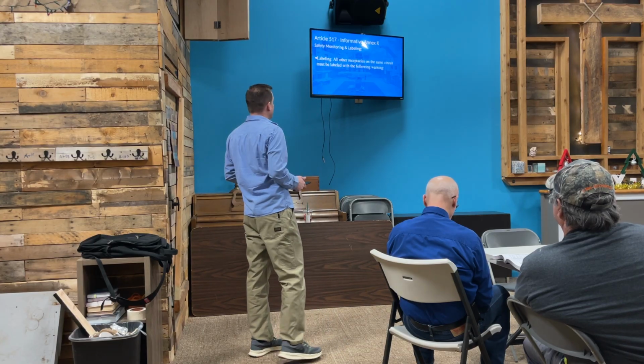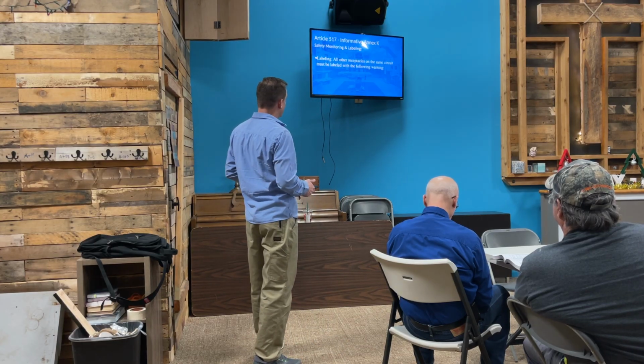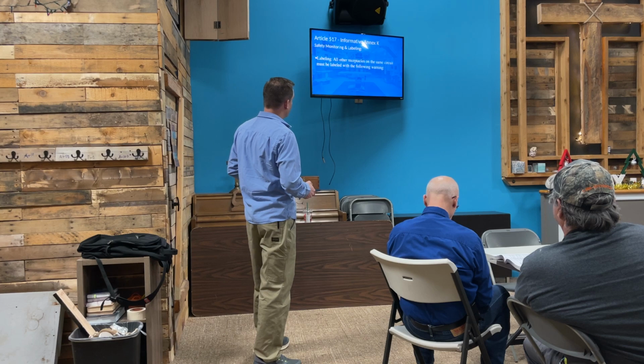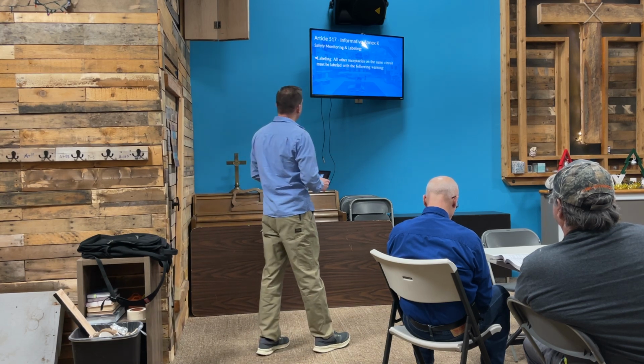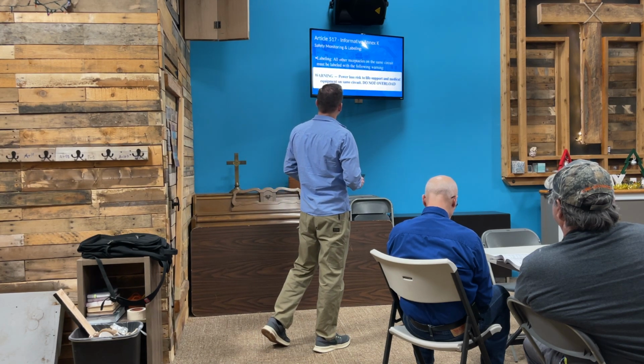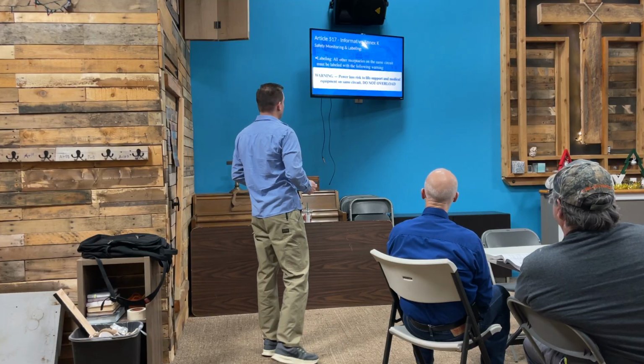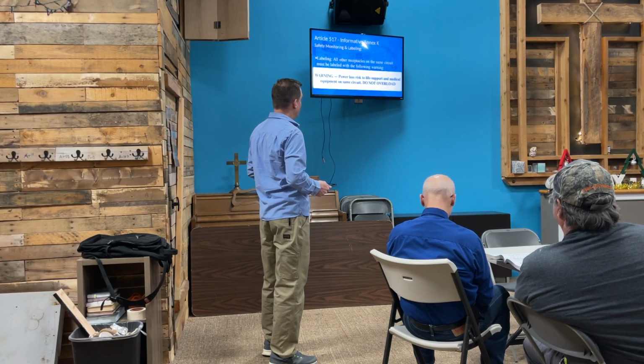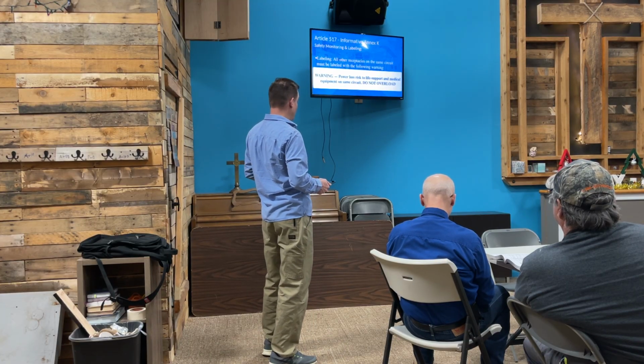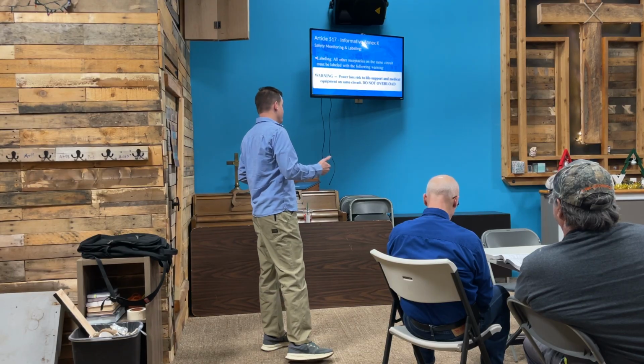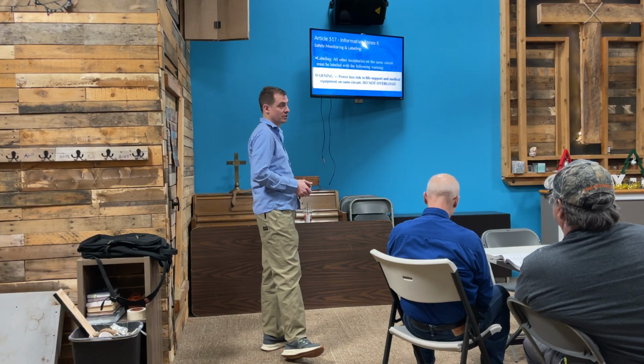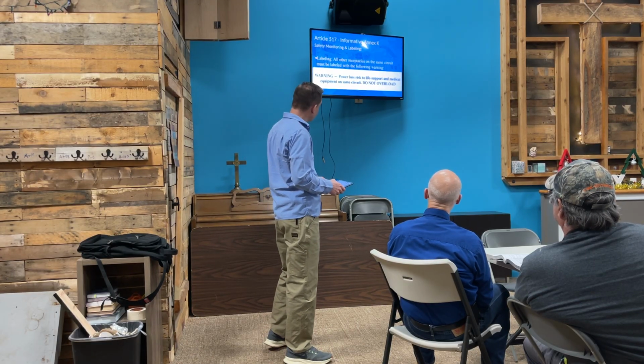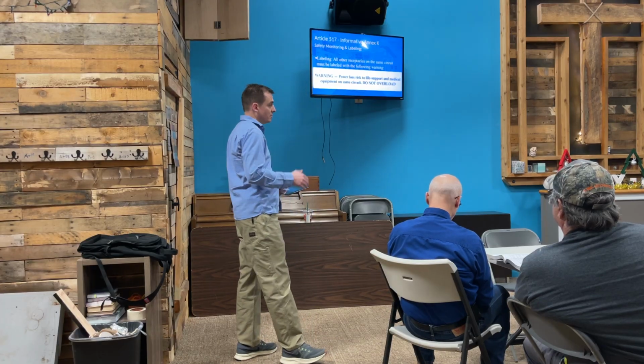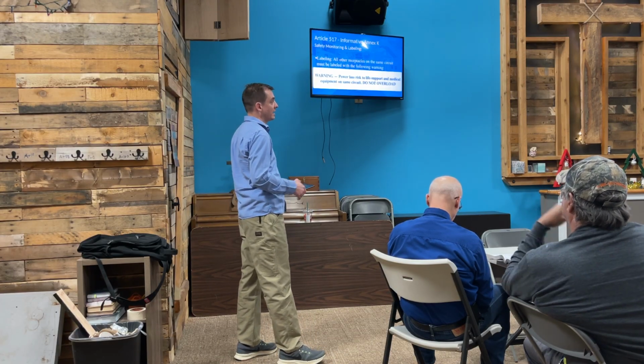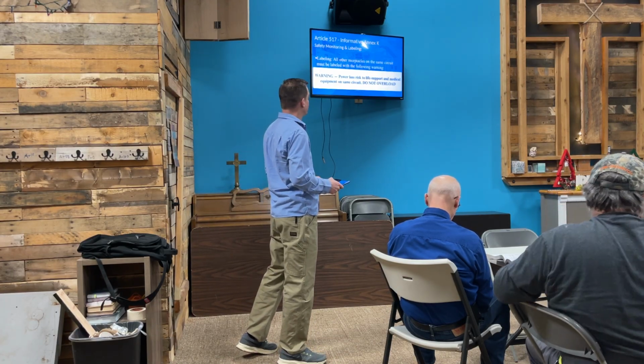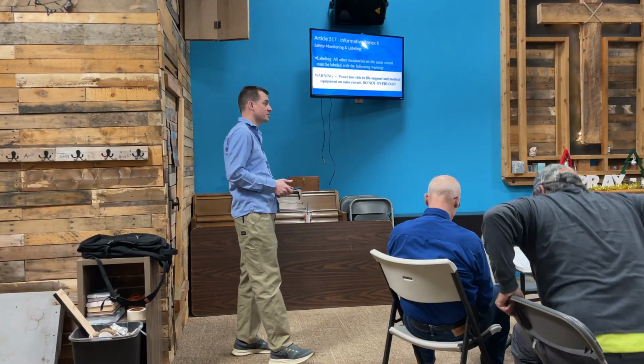This is it, so I did have this. Labeling: all other receptacles that are on the same circuit must be labeled with the following. Here's what it would say: Warning, power loss risk to life support and medical equipment on the same circuit, do not overload. So that's the end of this Annex K piece, but again, these are recommendations, not requirements.